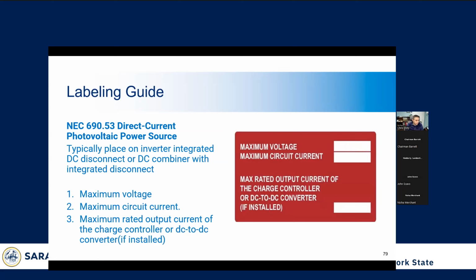Here we have the DC PV power source label, and that has to be on an inverter integrated DC disconnect or a DC combiner with a disconnect. This label gives important information to those who will maintain and repair the system in the future. So you have to label the max voltage, the max current, and the max current of charge controllers if installed with energy storage. NYSERDA is planning, I believe, or they have it out for public comment, to have a program for energy storage incentives if people install them in their house. So you may see that more and more frequently. So that's something to keep in mind.